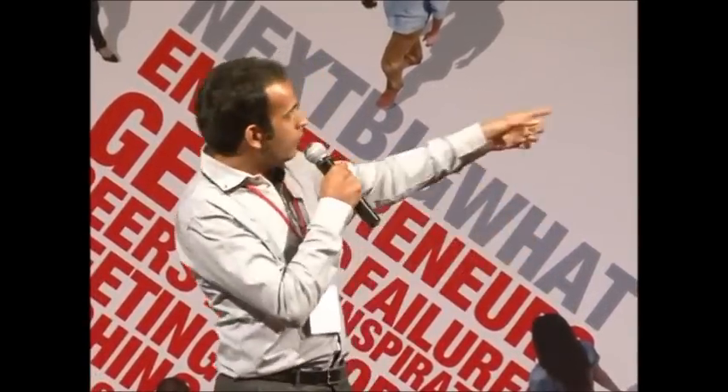I'm looking at my dad like he's some kind of hero. Basically what had happened was — this is a resin reactor. This is where we take the gum, it's called rosin — it comes from trees and naturally occurring extracts — put it in that resin reactor and heat it up with certain solvents like xylene, and you get resin, which is the gum for your paint. What had happened was during the trial runs, during commissioning, the temperature shot up because they added too much rosin. They panicked because they realized the temperature had shot up too late, then they brought the temperature down too fast. Because it cooled too quickly, the resin jammed up at the entrance of the resin reactor.